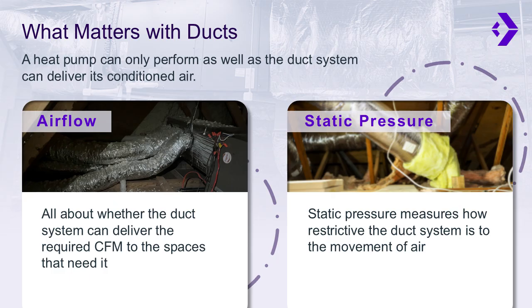It's not just about matching the heat pump to the home. It's about ensuring the ducts are sized with the same care. Properly sized ducts allow the system to operate efficiently, maintain consistent temperatures, and deliver comfort the homeowner expects. Duct sizing isn't an afterthought. It's a fundamental part of the load calculation and overall system design.